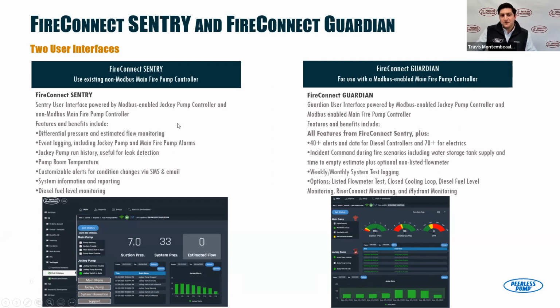But the beauty is, if you're doing a retrofit and you start with Sentry because you don't want to replace your main controller yet, when you're ready to upgrade to Guardian, all you do is add in that Modbus enabled main fire pump controller. You replace your existing one, and then you just connect an Ethernet cable between the main controller and the FireConnect jockey controller, the FCJC we call it. And now you can have a Guardian setup. It's that simple.